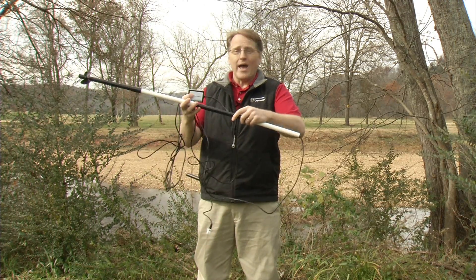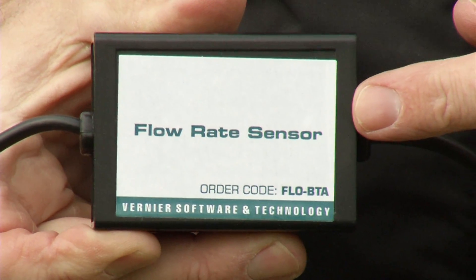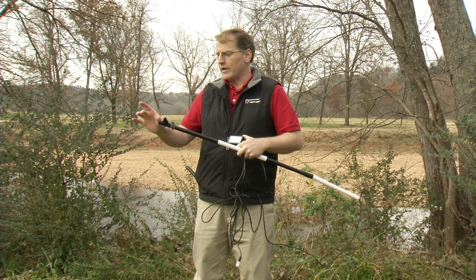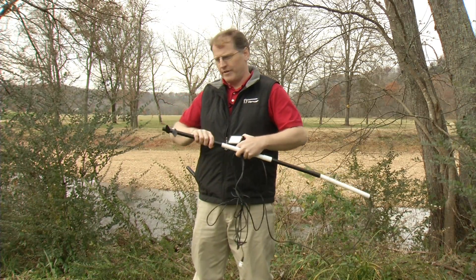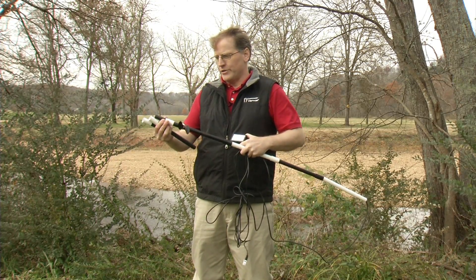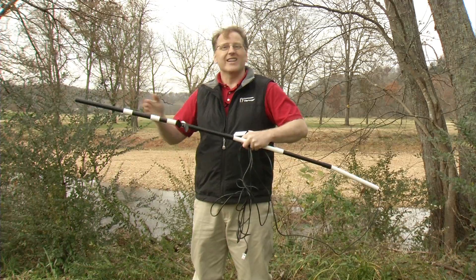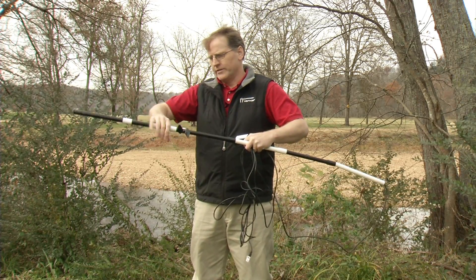The device can be wet up to this point — this is the electronics, and this part needs to stay dry out of the water. There are also three extension pieces that come with it. These are designed to allow you to place the sensor at different depths in the water, acting as a standoff from the bottom of the stream bed.